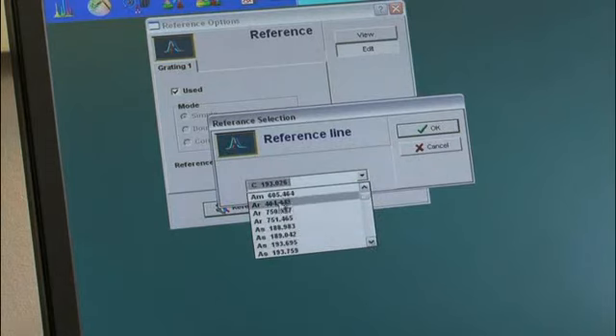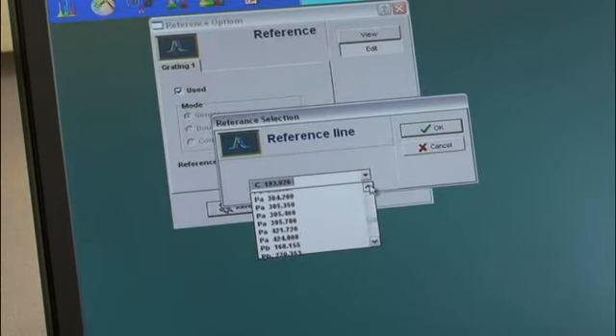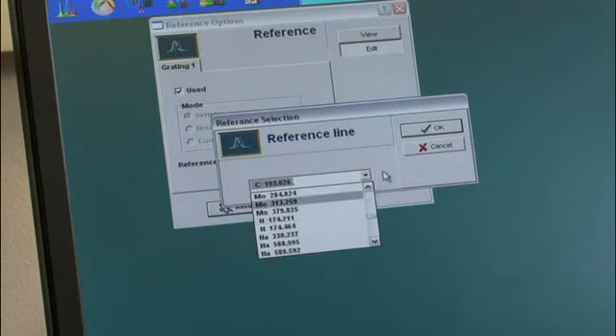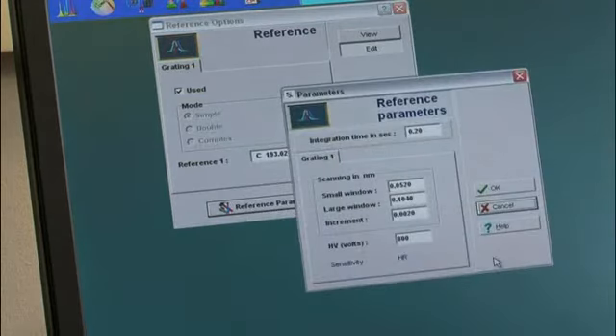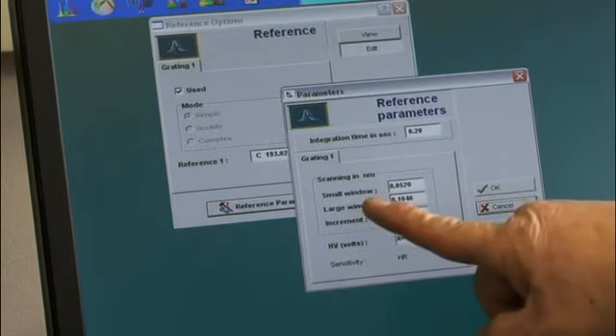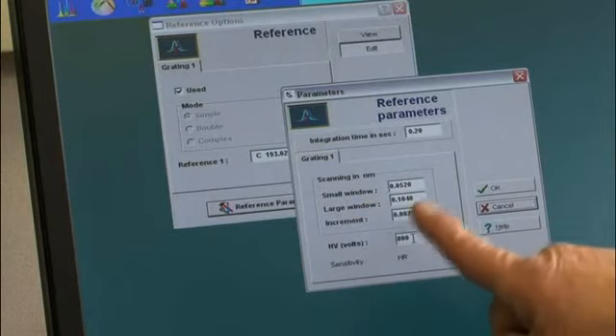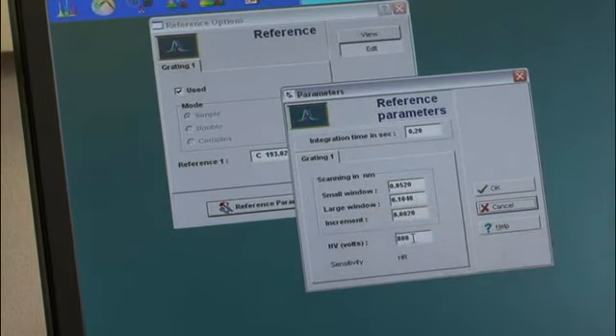Again, it would have to be either argon. There's an argon line at 404 right here, that's the most common one. Or if you were purging with nitrogen, you could use the 174 line. Right there, 211. Other parameters: if your reference is overranging, you can reduce the high voltage right here. Again, this is the voltage on the photomultiplier tube, and that reduces its sensitivity. This will show you the size of the window that it's scanning for that carbon peak. If it doesn't find it in a small one, it goes to a large one and looks for it there. Integration time, you can leave that at 0.2.